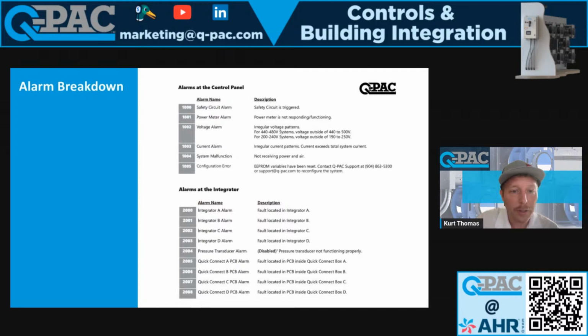Power meter is not responding. So we have a power meter. If you see code 1001 show up, you may also see code 1004. That doesn't mean that your fans are not operating. That just means that, hey, our meter that monitors voltage, current, and power consumption, something's going on. Our PLC is not able to communicate with it. And basically, you need to check the wire between it. That device does communicate via Modbus to our PLC.